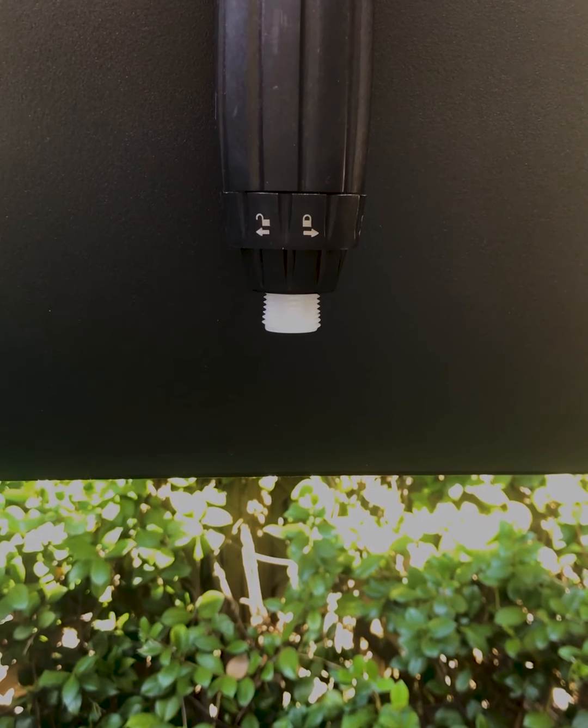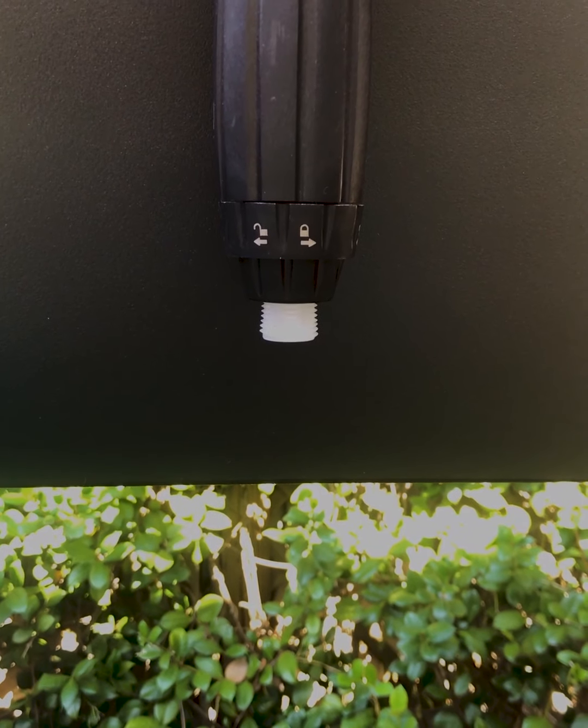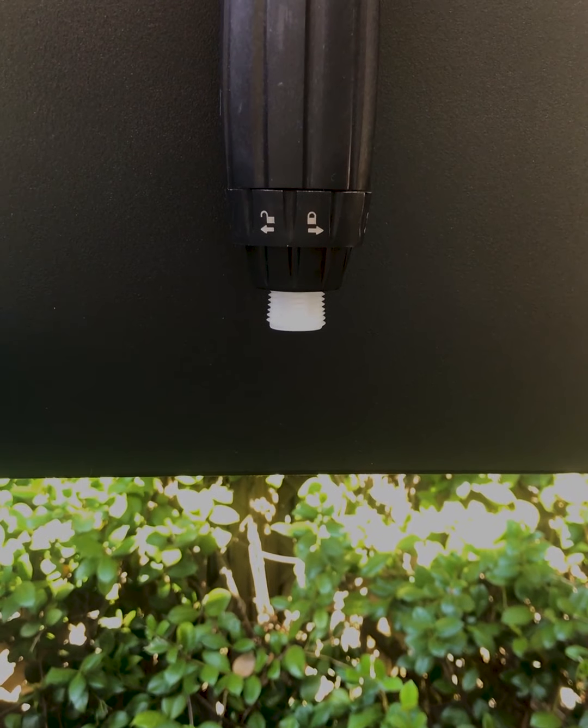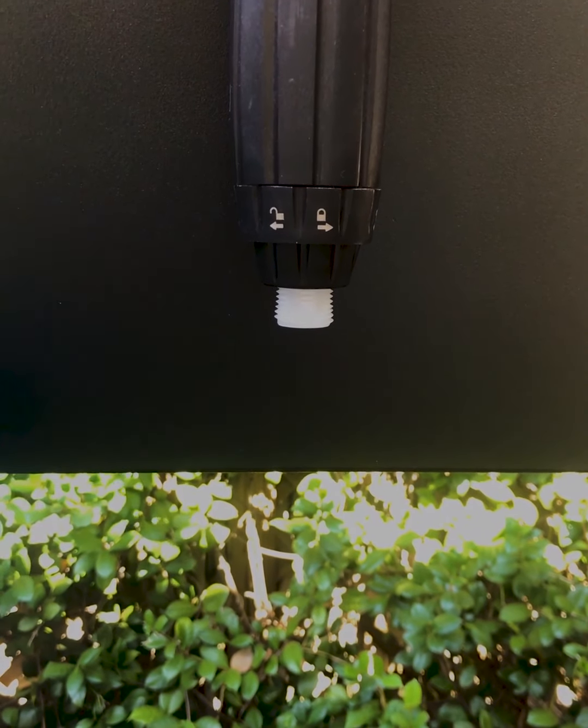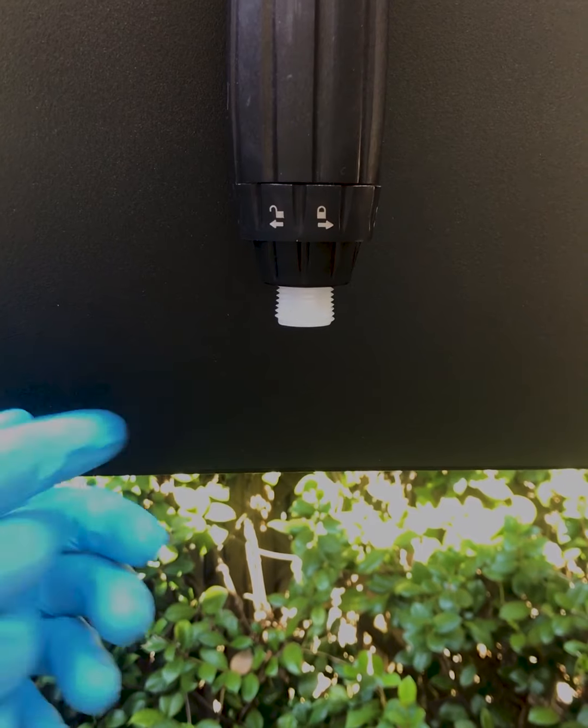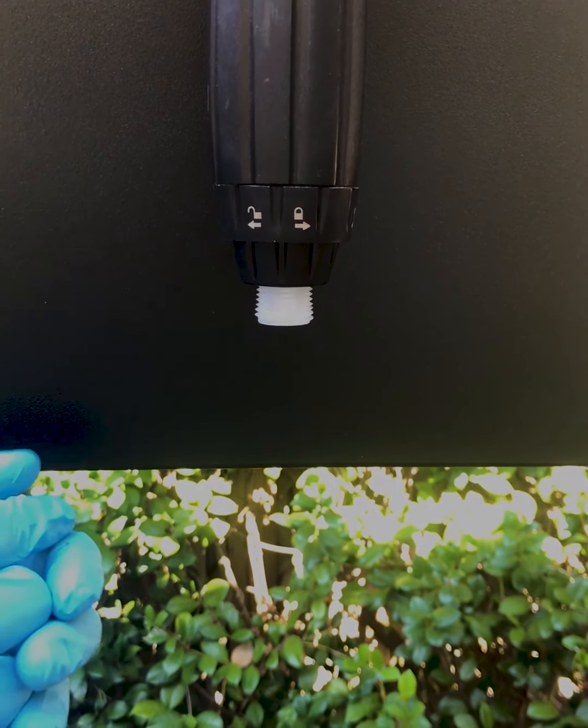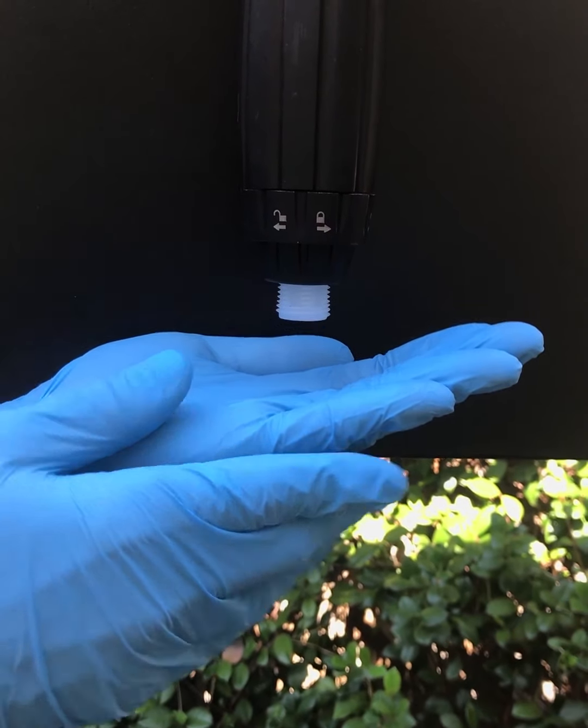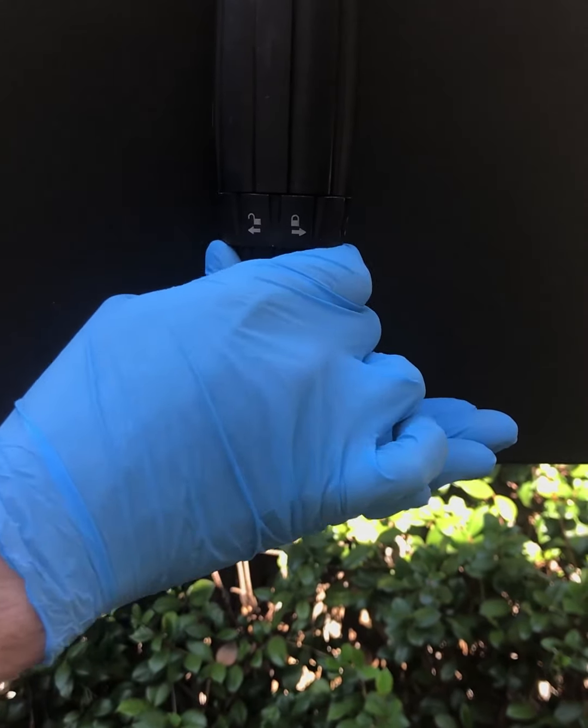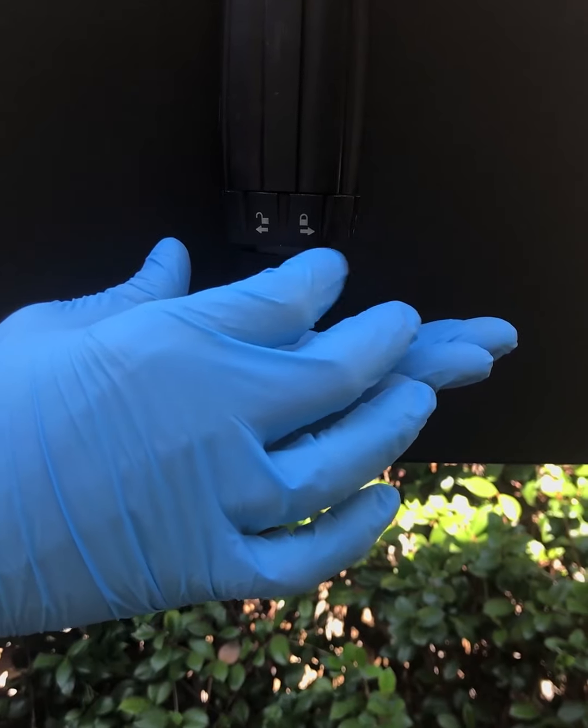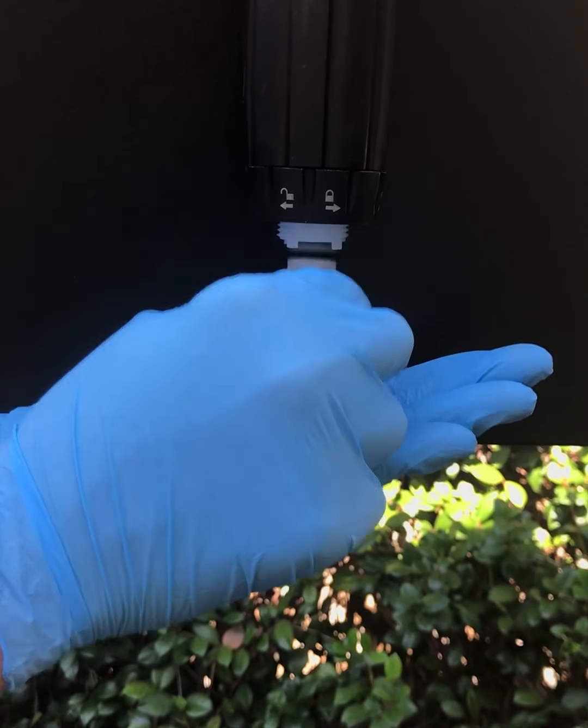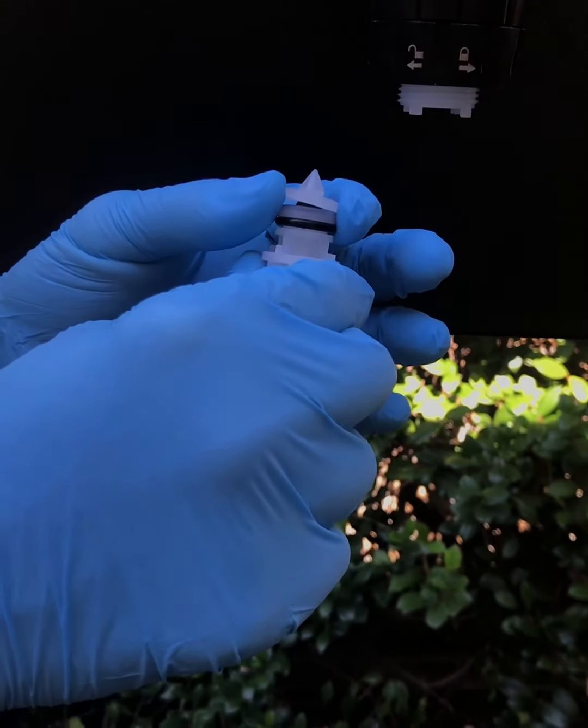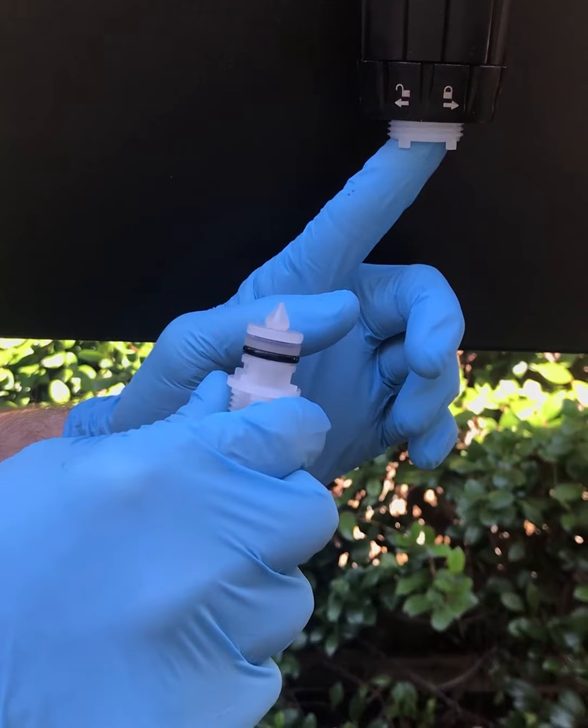Now we're going to remove and inspect the check valve. Keep in mind, there may still be undiluted chemical inside the stem assembly, so take all proper precautions when handling these components. What we're going to do is locate the check valve nut at the bottom of the stem assembly and remove, keeping one hand underneath all the parts in case something is to fall down during this process. Remove the check valve nut and pull down on the check valve barb. Now the check valve assembly may come with the barb or it may stay up inside the stem itself.